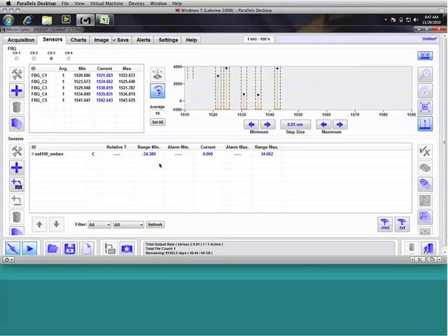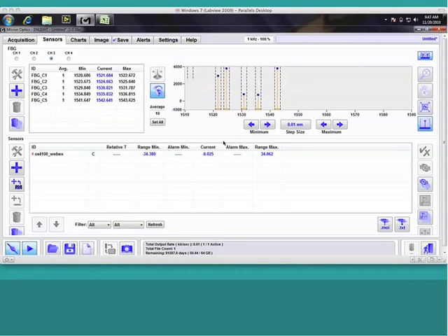And let me add in there, when you create a new sensor using the templates or putting it in manually, ENLIGHT will automatically take a snapshot of any of the referenced FBGs or external sensors within that sensor, and it will create reference values for you, which is why our delta T measurement is coming up as 0. It took a snapshot of FBG C3 at its current value and is now using that within the formula.